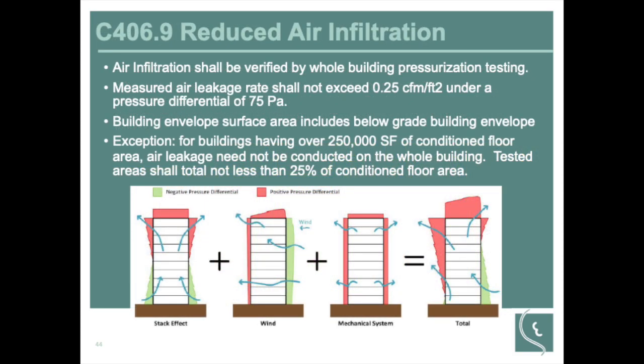Another path that they allow for, another option for compliance for prescriptive, is reduced air infiltration. So here we are going to pressure test the building envelope. Sean's got all kinds of stories from other locations that he's been to that building envelope failures, just, they didn't finish the envelope. But it was above the ceiling, so no one noticed. And all the havoc that caused with all the HVAC systems that couldn't keep up because there was a giant hole in the outside.